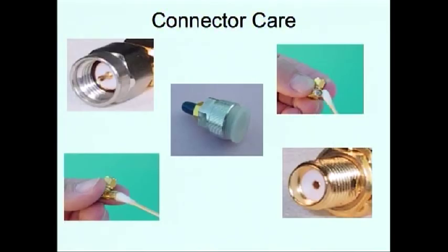Keep connectors clean. Protect connectors with plastic end caps. Keep connector temperature same as the analyzers. Clean surfaces first with clean, dry, compressed air. Use lint-free swab or brush. Rotate only the connector nut. Do not cross thread the connection. Do not twist connector body to make connections. Do not mate different connector types.